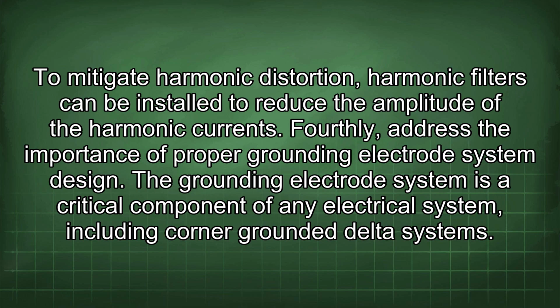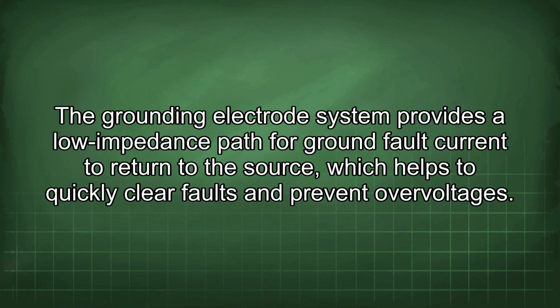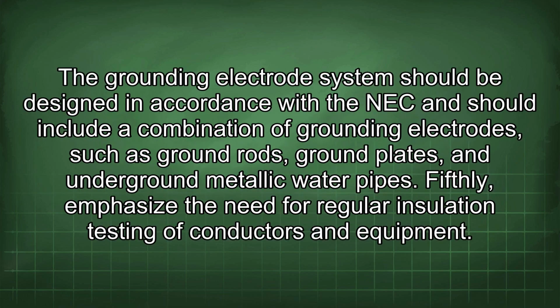Fourthly, address the importance of proper grounding electrode system design. The grounding electrode system is a critical component of any electrical system, including corner-grounded delta systems. The grounding electrode system provides a low impedance path for ground fault current to return to the source, which helps to quickly clear faults and prevent overvoltages. The grounding electrode system should be designed in accordance with the NEC and should include a combination of grounding electrodes such as ground rods, ground plates, and underground metallic water pipes.